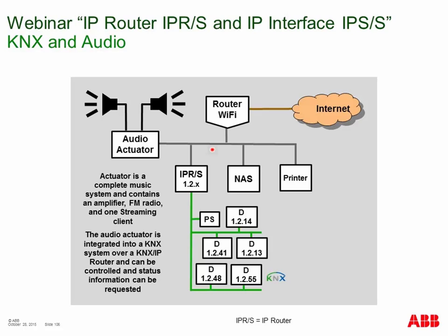Regarding audio and video control: KNX bus speed is limited to 9,600 bits per second, so audio or video data cannot be sent via KNX, but commands can — like changing volume, calling a playlist, or changing a web radio station. On the KNX market, some manufacturers offer audio actuators connected to the IP network with multi-zone speaker support. Via KNX, commands are sent to the IP router, which passes them into the IP network to control the audio device. Feedback such as volume status, artist name, and playlist name is returned to the KNX world.